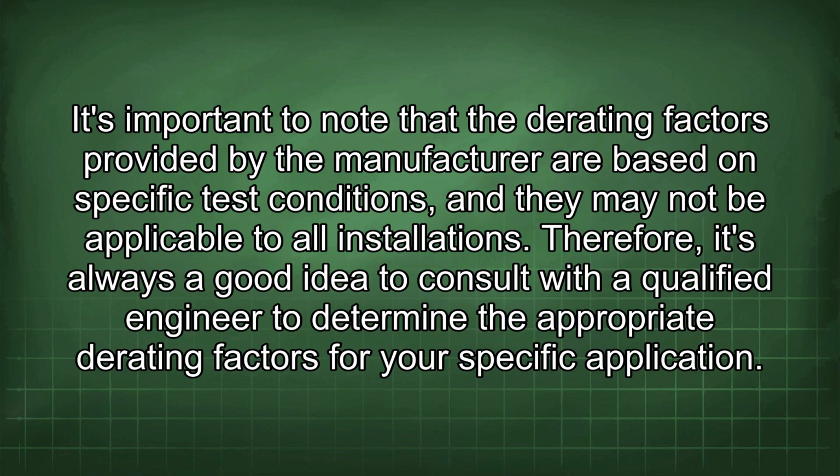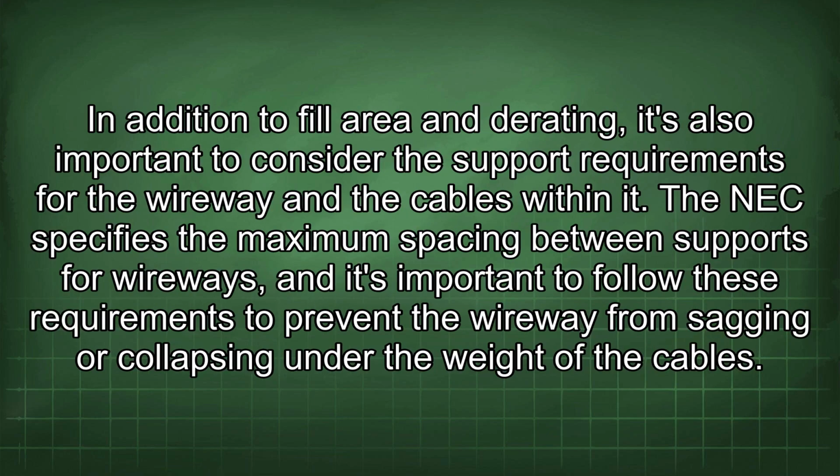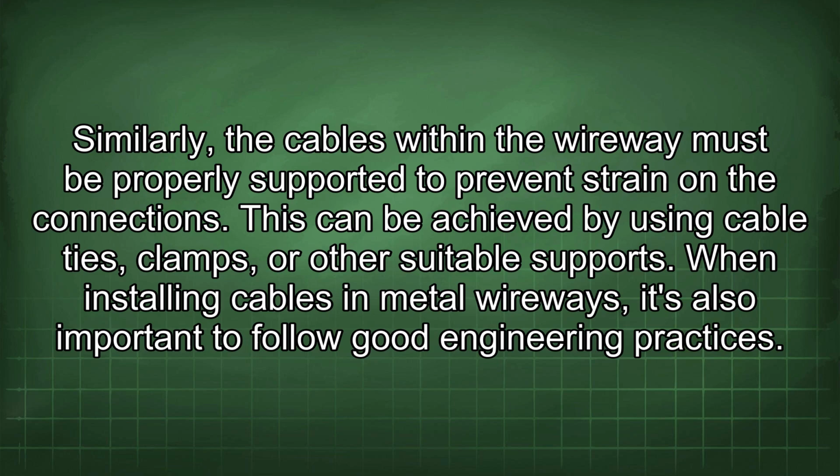In addition to fill area and derating, it's also important to consider the support requirements for the wireway and the cables within it. The NEC specifies the maximum spacing between supports for wireways, and it's important to follow these requirements to prevent the wireway from sagging or collapsing under the weight of the cables. Similarly, the cables within the wireway must be properly supported to prevent strain on the connections. This can be achieved by using cable ties, clamps, or other suitable supports.